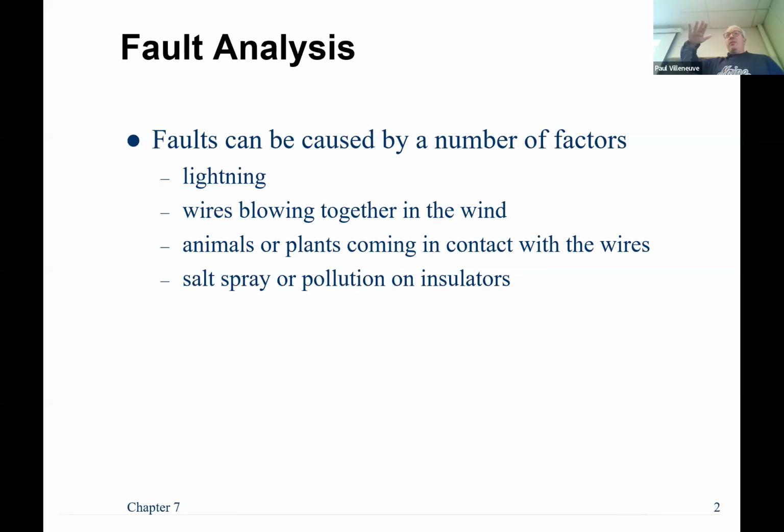You'll see some bushes that are maybe 3 to 4 feet in height, but you don't see tall trees growing in there because they will spray a pesticide or mow the area down about every 5 years to ensure they don't have trees growing up, because eventually over time the trees would go up into the line, potentially causing some problems. Animals, right? Birds can cause problems. More likely it's going to be a ground-based animal. What I mean by that is squirrels, raccoons. If you're down south, snakes are notorious for causing that. Because if you think of a snake, right, it has a really long body.